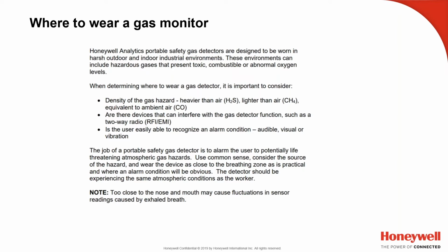So when determining where to wear a gas monitor on your person, it's important to consider the density of the gas hazard. H2S is heavier than air, methane is lighter than air, and CO is equivalent to ambient air. But the caveat with CO is that it usually comes out of an internal combustion engine, so it's hot and will rise, and then as it cools, it settles into basically the equivalent density of air.